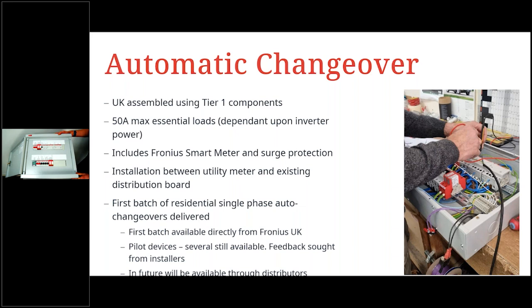So we have 50 amps on essential loads, which are going to stay live during a grid failure, and we have the other 50 amps for the non-essential loads. We'd suggest things like EV chargers, heat pumps, and other big loads are put on the non-essential side so that you're not draining the battery excessively quickly with those.